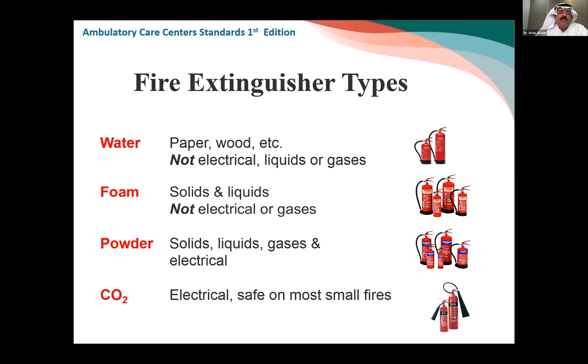Why do we need the carbon dioxide? Because if you have energized equipment or machines, you cannot use any of the others. You need to use the carbon dioxide because it's non-conductive. Please make sure the carbon dioxide is only used, for example, in the X-ray machine, if you have MRI or CT, or a very specific server room, the ones which are energized, and you don't want to waste it. However, if you disconnect the power, you can use powder or any one of the other extinguishers.